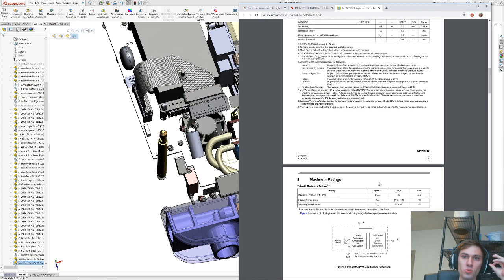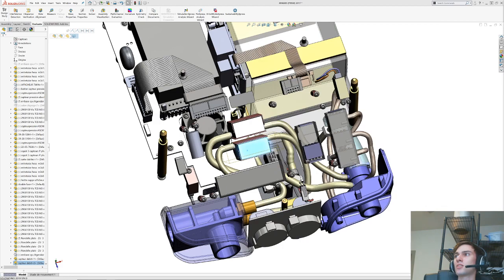So that's like 1/50th of 14.7 psi. Accuracy. Maximum pressure, 75 kilopascals. It's going to be kPa gauge. No, that's going to be delta. So that's going to be like 10 psi. So we could definitely use something like this. This is absolutely something that we could use. That's good. That makes life a little easier.